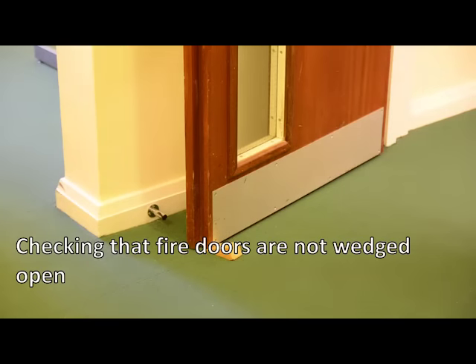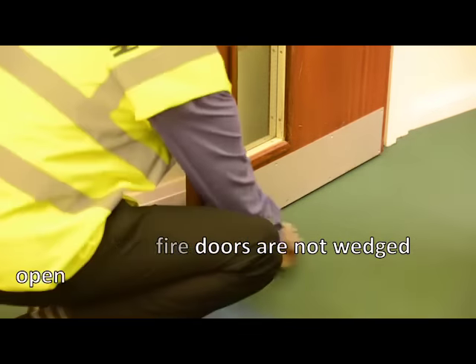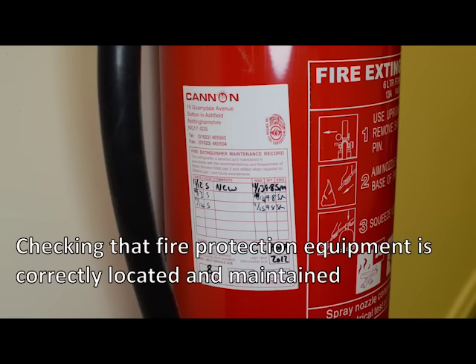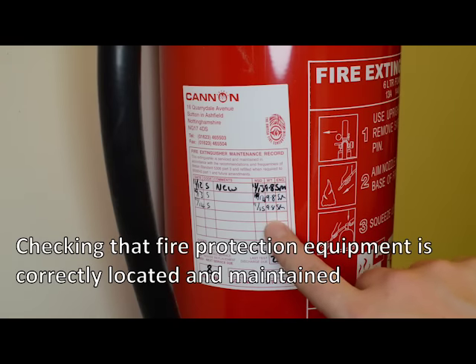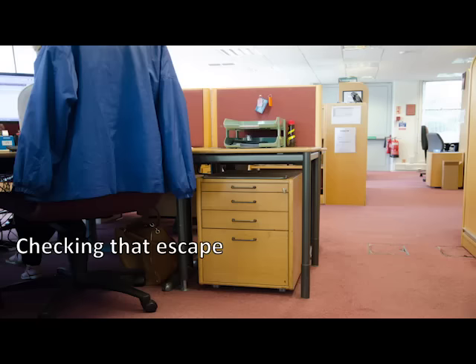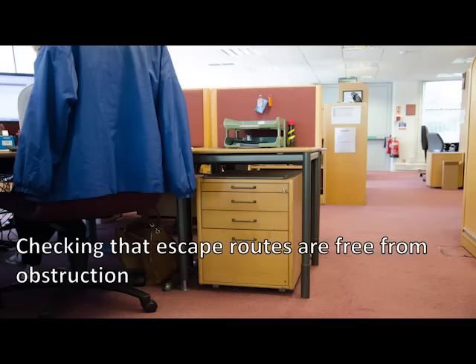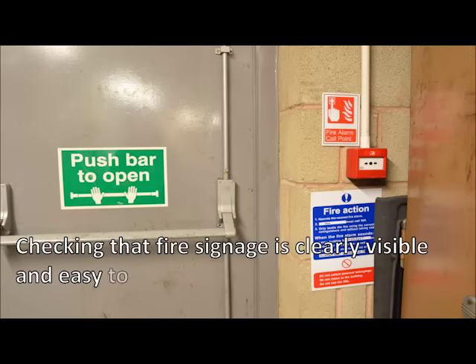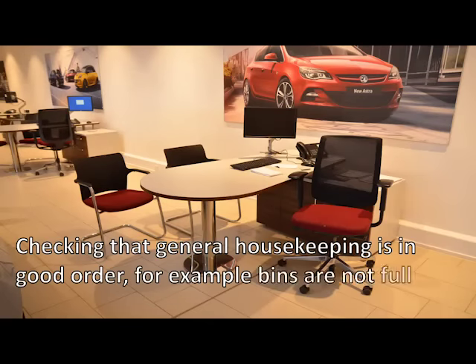Checking that fire doors are not wedged open. Checking that fire protection equipment is correctly located and maintained. Checking escape routes are free from obstruction. Checking that fire signage is clearly visible and easy to understand. Checking that general housekeeping is in good order. For example, bins are not full with paper and cardboard.